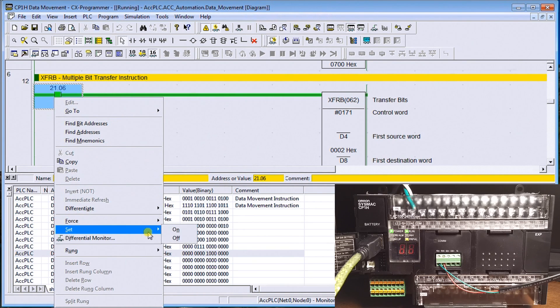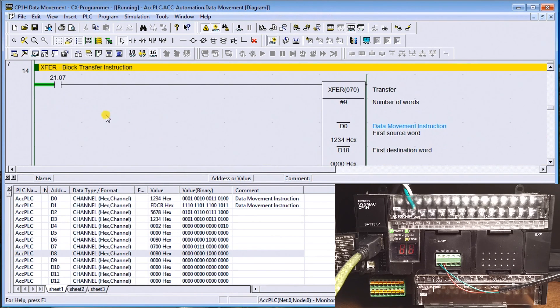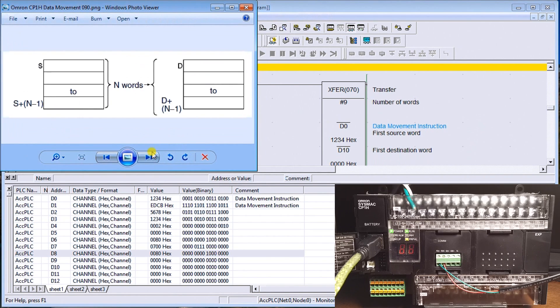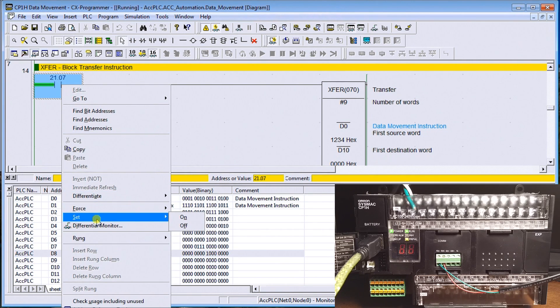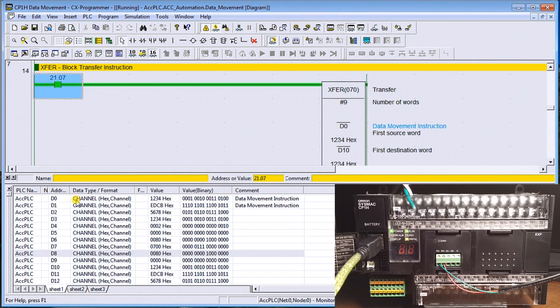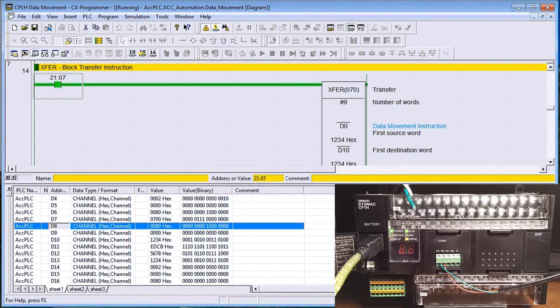Next is Block Transfer (XFER). This takes a number of words from one area and copies them into another area. We specify the number of words, starting at data memory zero, take nine of them, and move them over to data memory ten. Turning it on, data memory zero through eight are all transferred into data memory ten and onward — an exact duplicate of what was above.